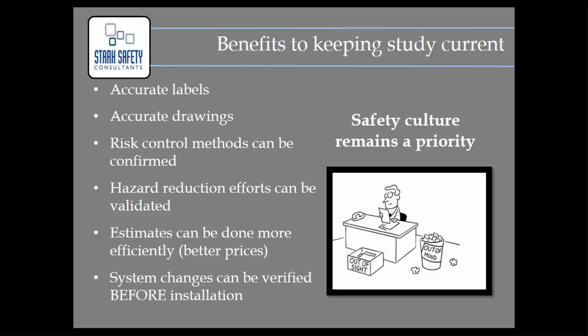A stereotypical example: all the focus is on doing an arc flash study. We're going to update our system, improve our training program, get PPE for everybody. Then what's the normal human reaction? Nothing changes. Over time we lose focus. There are system changes going on that we're not updating, and we still have labels out there, and the workers are aware it may not be accurate because they know it's not connected to the upstream device it used to be. Our focus starts to wane and we lose confidence in the information, which leads us to think less of the importance of the PPE and our safety program overall. Then the 5 years comes back around and suddenly everyone gets high priority again, and it's back in the forefront.